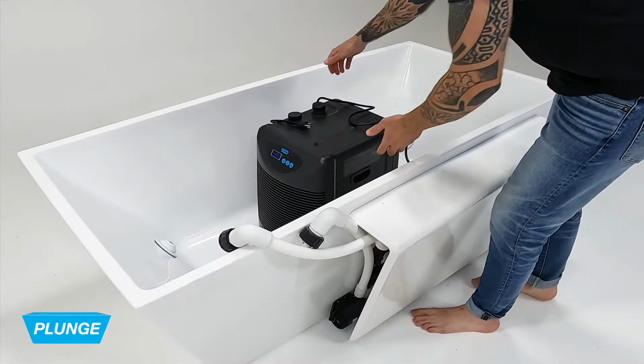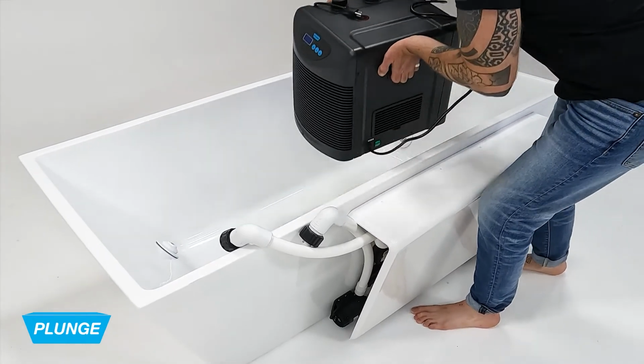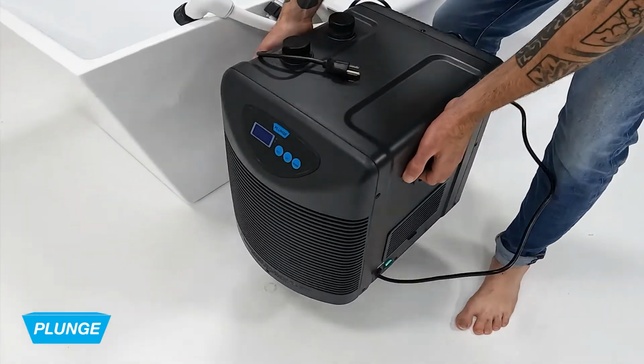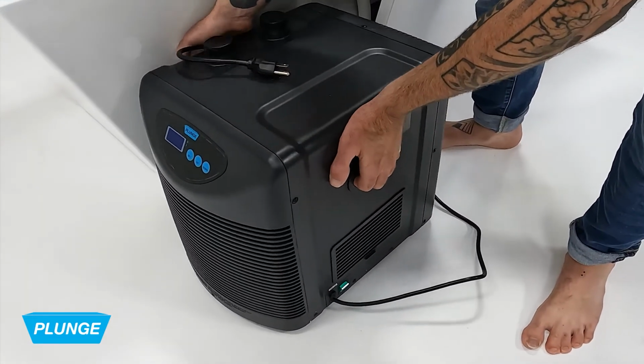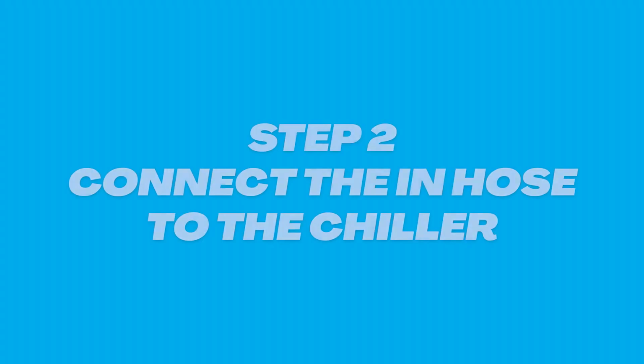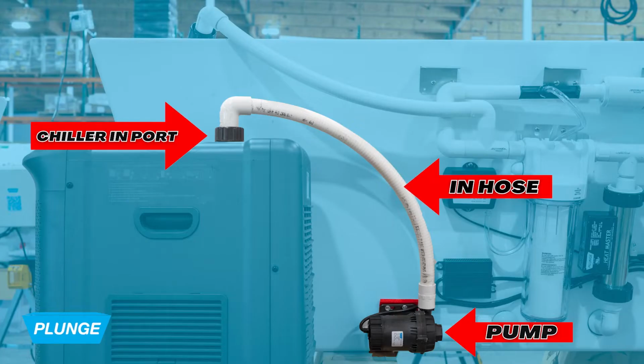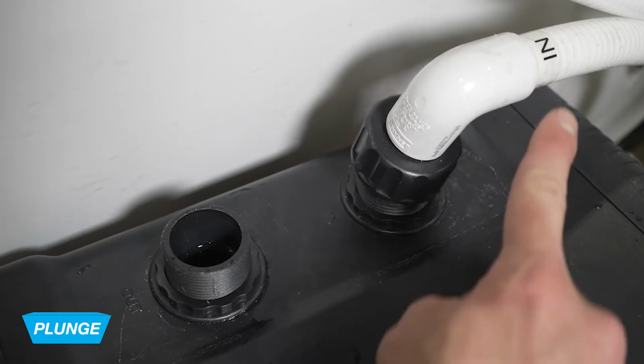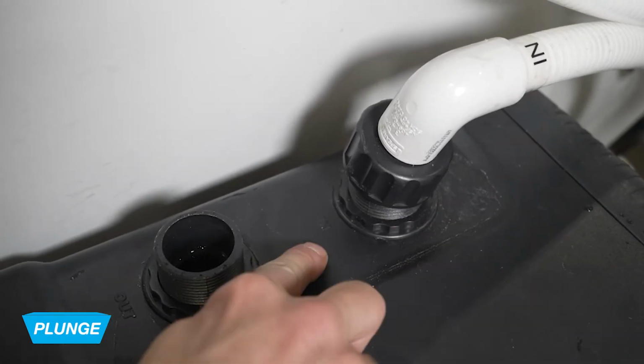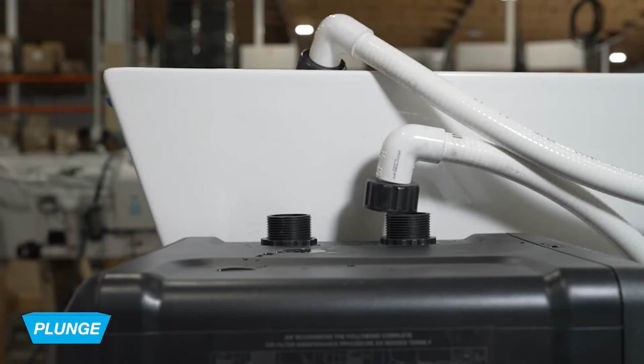Prior to setting up our plunge, we want to assure that the chiller is stable for at least 3 hours. Step 1. We're going to remove the chiller from the tub and place it on the component side of the plunge. Step 2. Before filling up the plunge, we want to connect the in hose from the pump to the in port on the chiller.